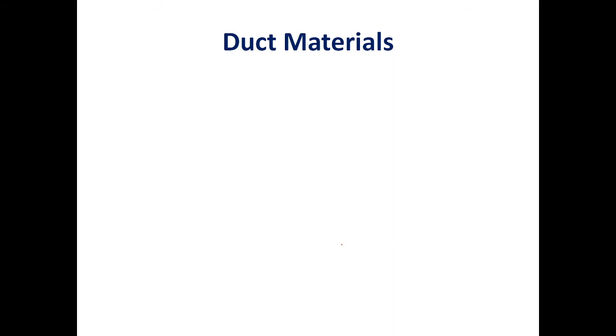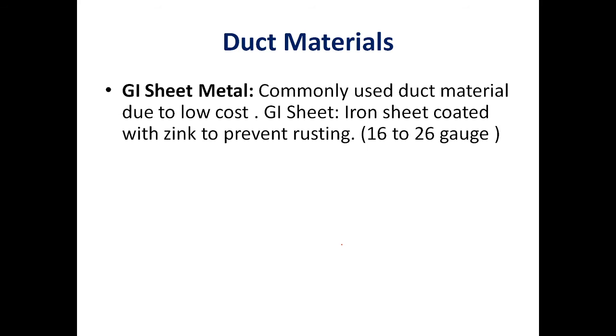Now let us look at duct materials. The most commonly used material is galvanized iron (GI) sheet metal, preferred for its low cost. Galvanized iron is iron sheet coated with zinc to protect it from rusting. Different gauges are used, ranging from gauge 16 to gauge 26. Higher pressure requires a lower gauge number, because a lower gauge number means greater sheet thickness.